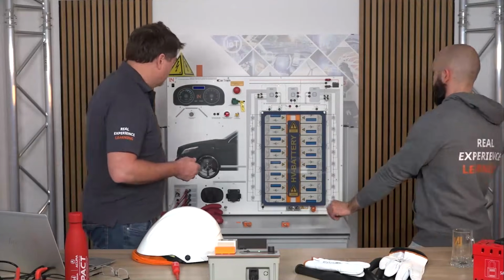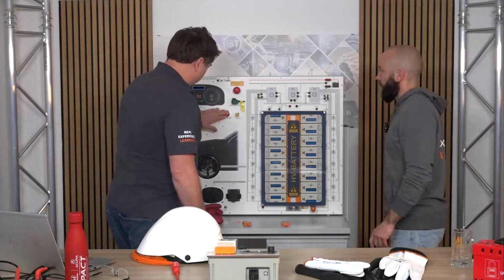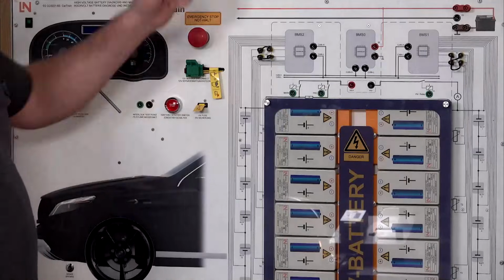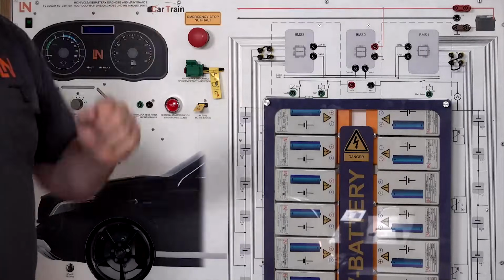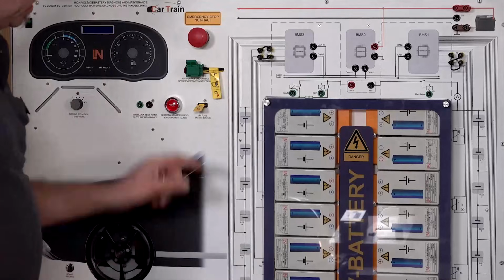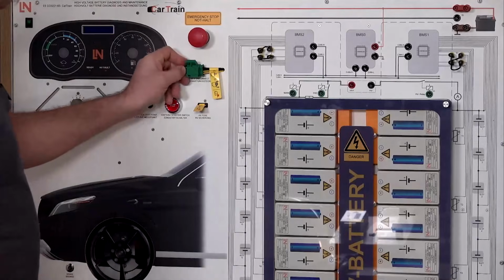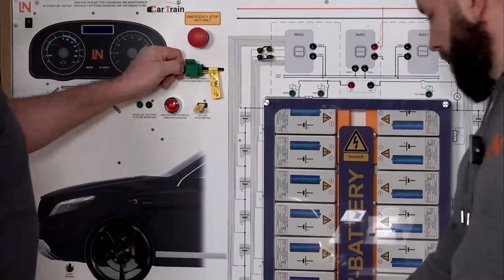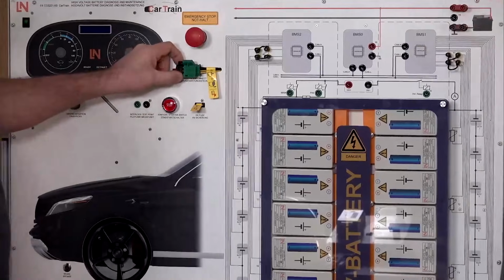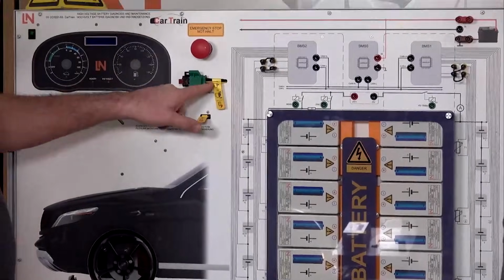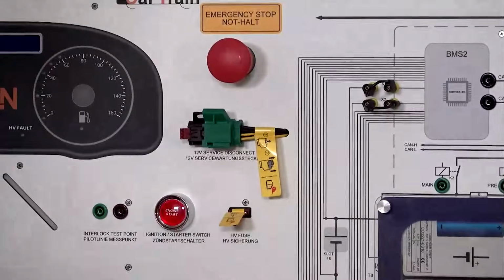Let's do it. First, I've switched the system off and put the key inside the lockbox. But on this system, we're also going to remove this green connector here. I can just pull that out, and we can see there are 4 cables here - this is part of our interlock.